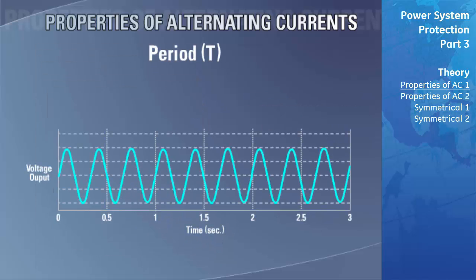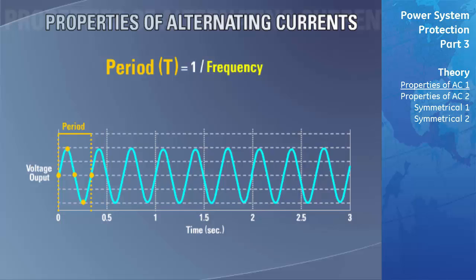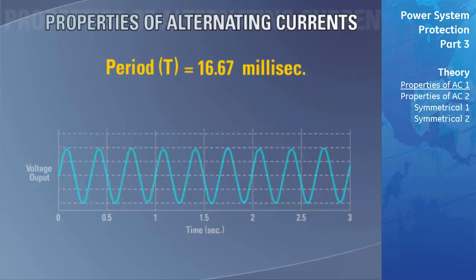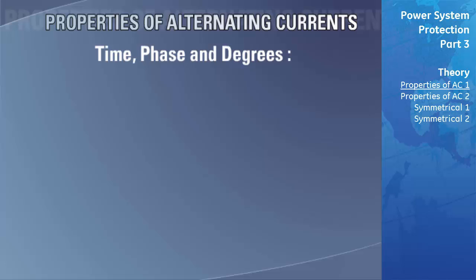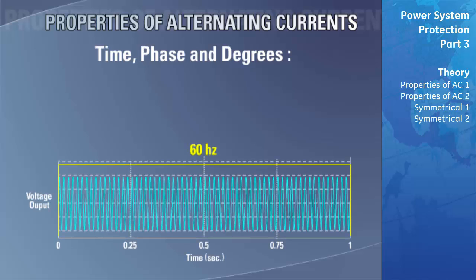To generate one cycle of alternating current, the exciter must complete one revolution. The time taken for the resulting waveform to go through one complete cycle is referred to as the period, represented by the symbol T, and equals one second divided by the frequency. For example, the period of a 60 hertz waveform is 1/60 = 16.67 milliseconds.